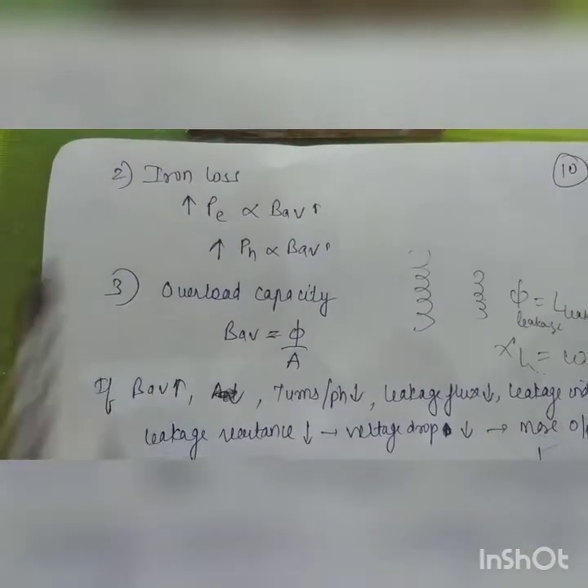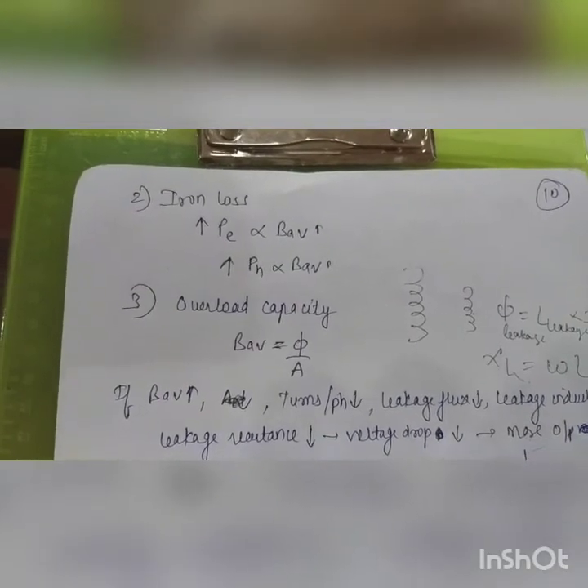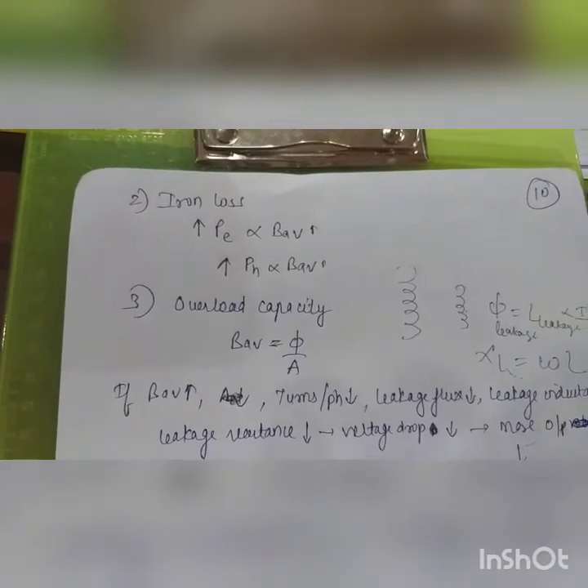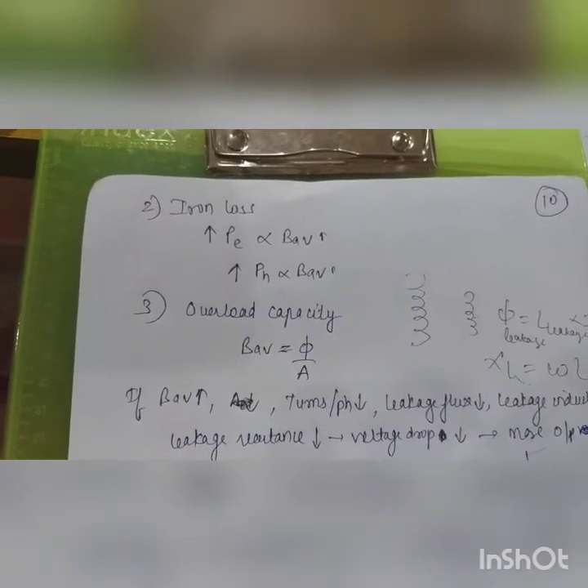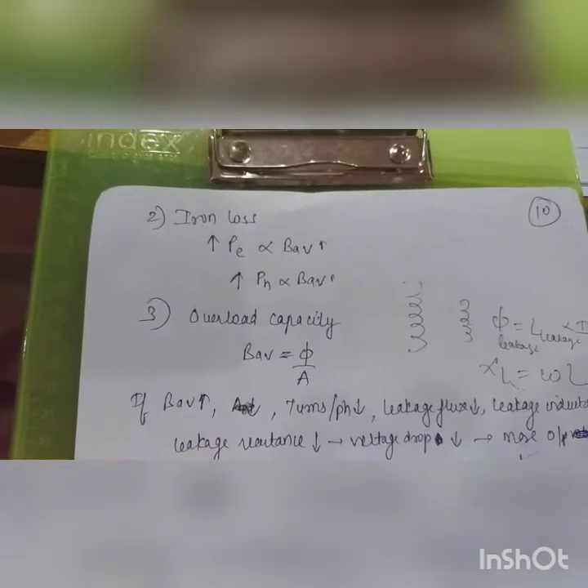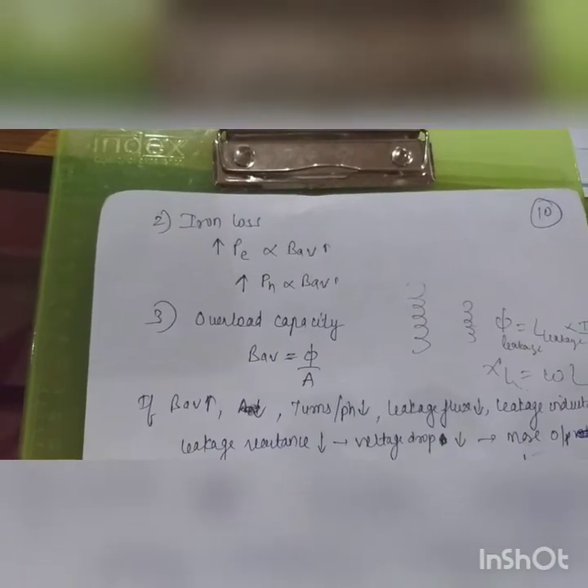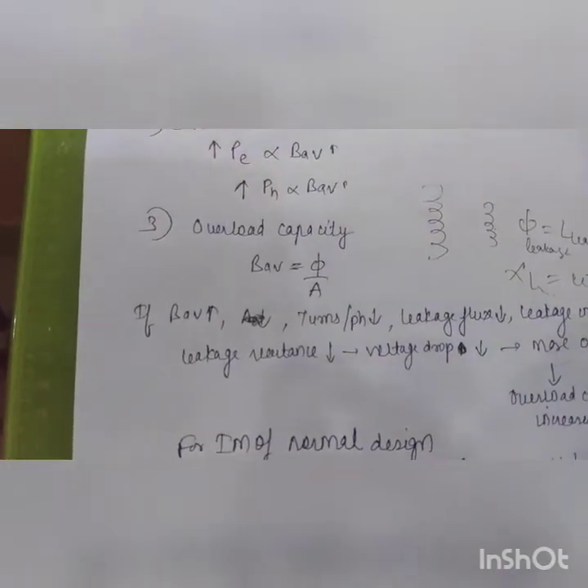The next factor is iron loss, which has two sub-types: hysteresis loss and eddy current loss. Both depend on average flux density. If high average flux density is used in the induction motor, both eddy current loss and hysteresis loss increase, generating more heat.